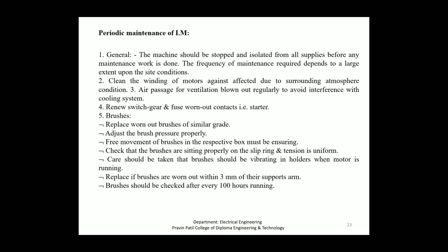Second, clean the winding of the motor against the surrounding atmospheric conditions. Third, blow out air passages for ventilation regularly to avoid interference with the cooling system. Next, renew switchgear and fuse worn out contacts, that is the starter.